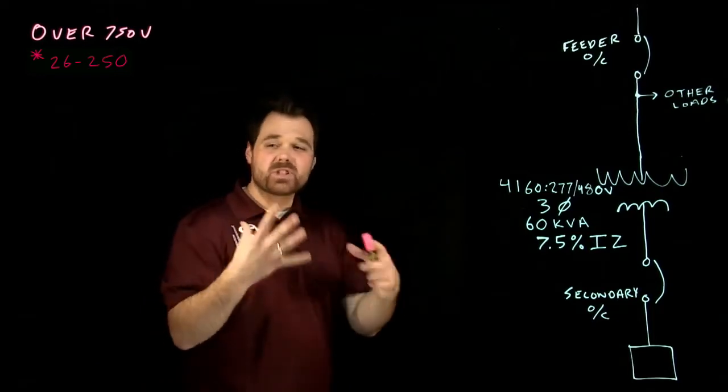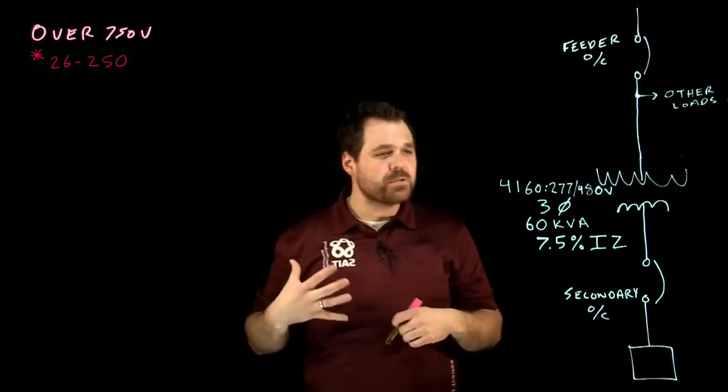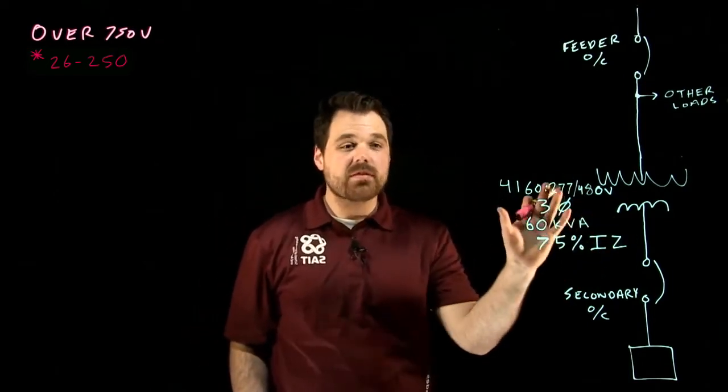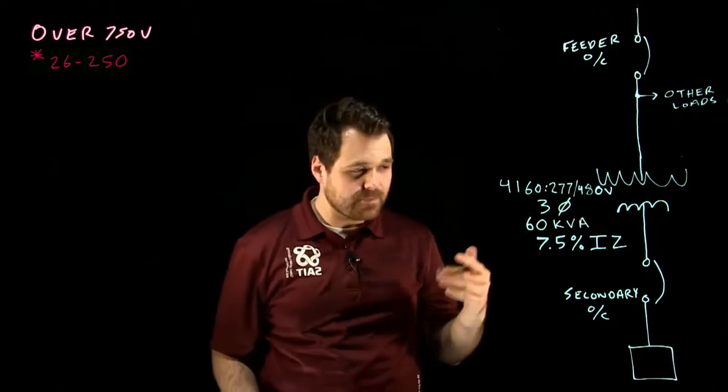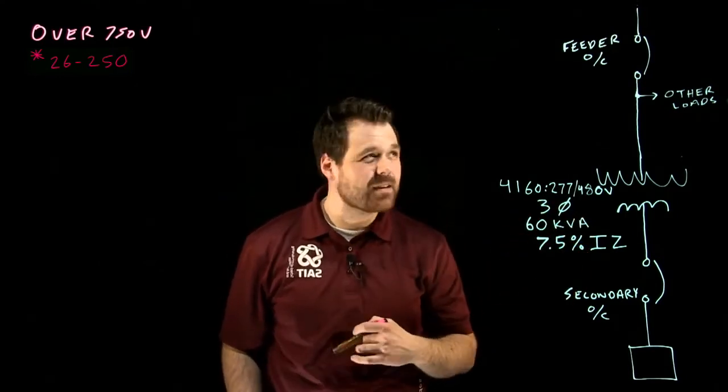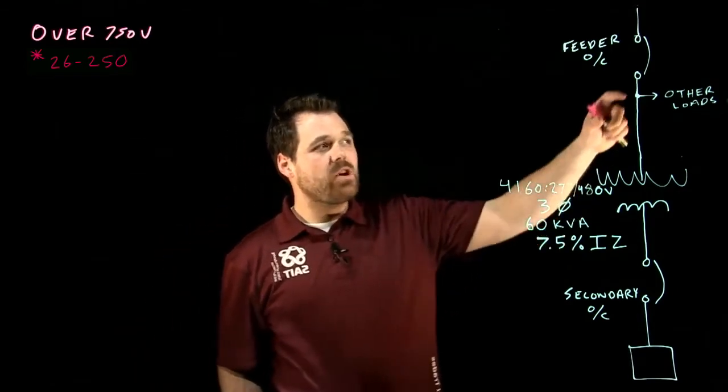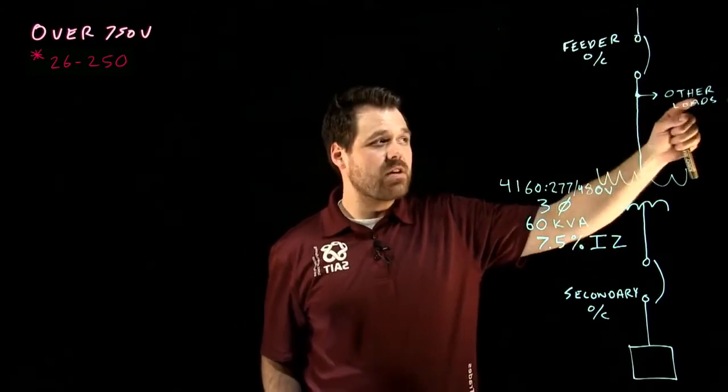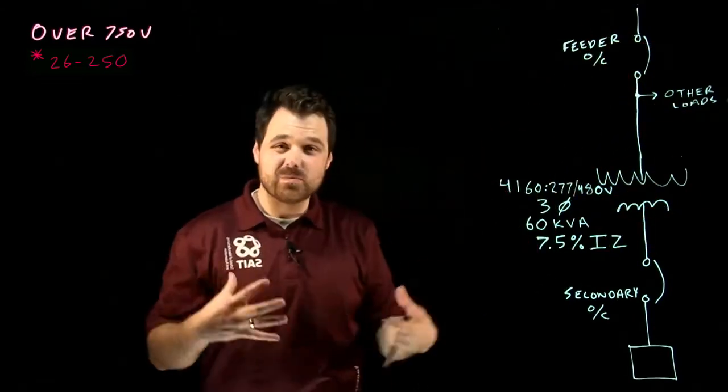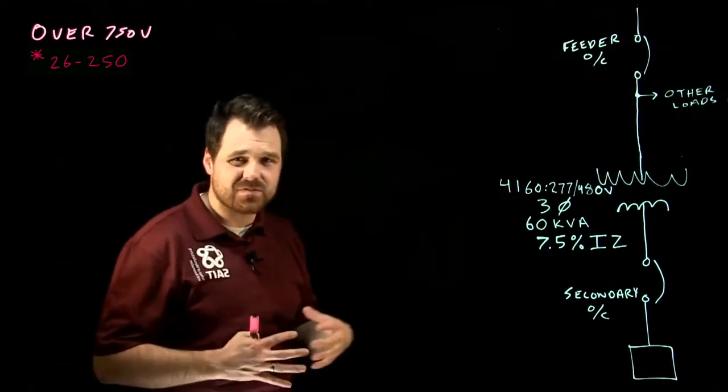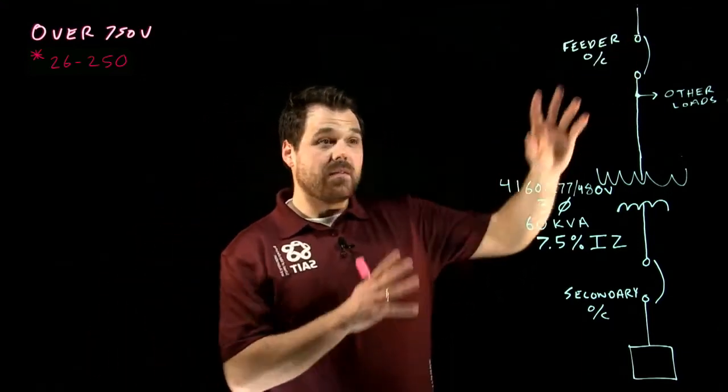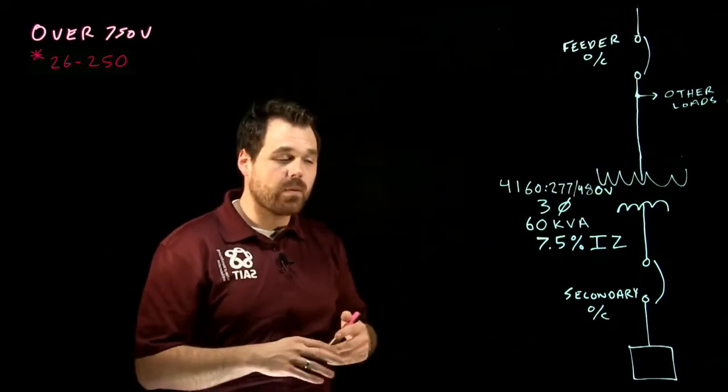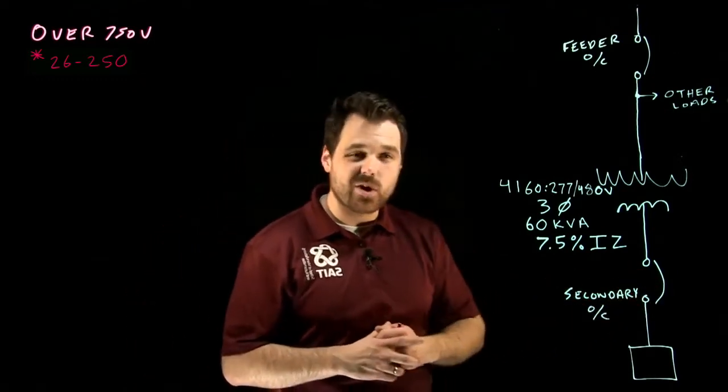In this situation right here, we're going to deal with all 26-250. We're dealing with a 4160 to 277/480, three-phase transformer, 60 kVA, with a 7.5% IZ. In this situation here, we've got a feeder overcurrent which is protecting this transformer as well as other loads. We want to make sure that this feeder overcurrent isn't too big, so it still provides us with the appropriate short circuit protection for our transformer. If it doesn't, we may need to add an individual primary overcurrent protection for the transformer.